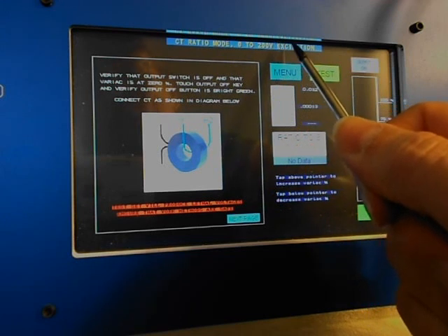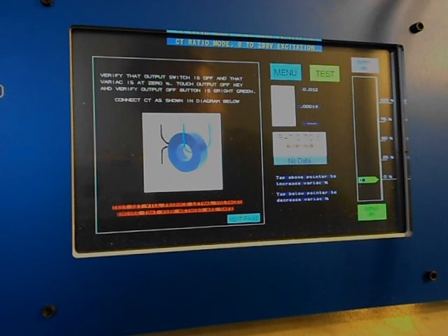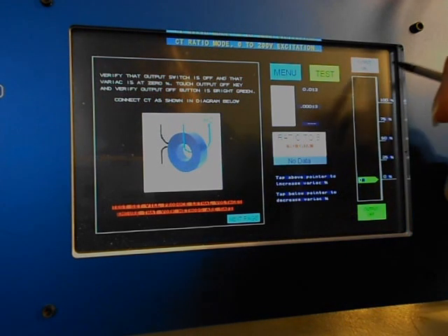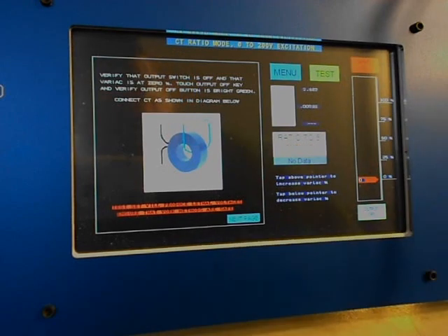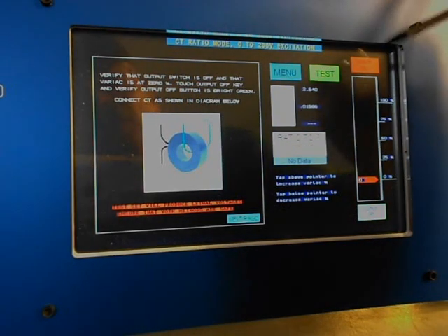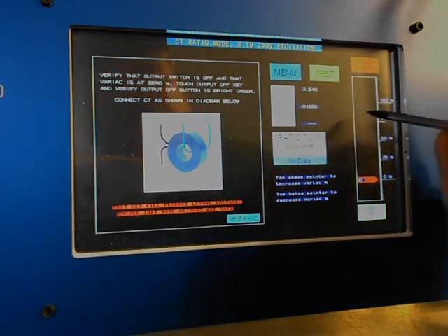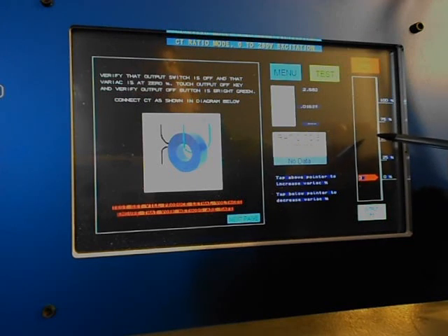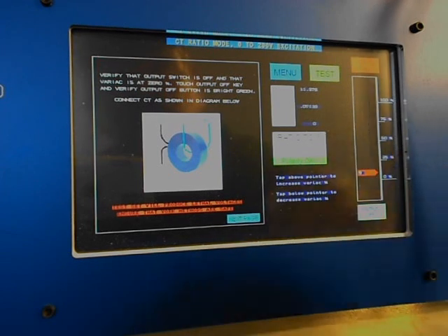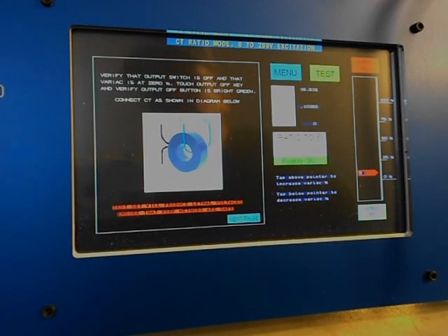The only time you'd need the 0 to 1000 volt range is if you had a large CT and a generator that was more than 10,000 to 5 in ratio. Okay, so all I have to do here is turn the output on. That turns red when the output is on. Tap above the variac pointer to raise the variac.